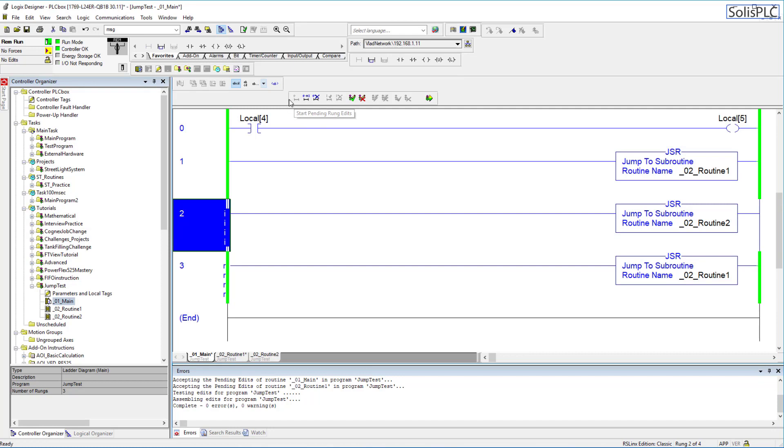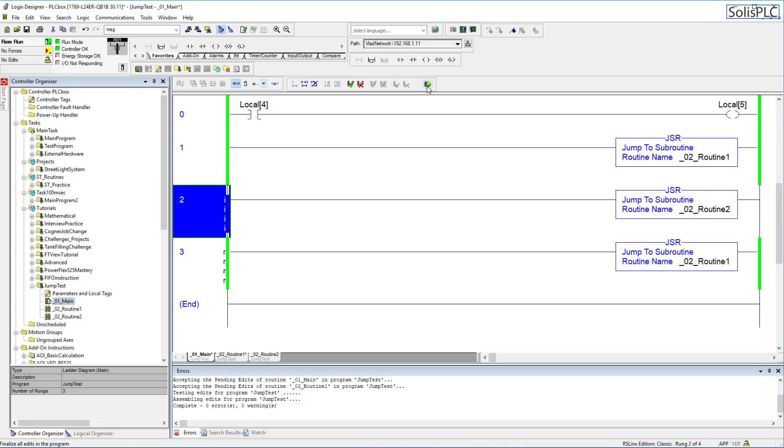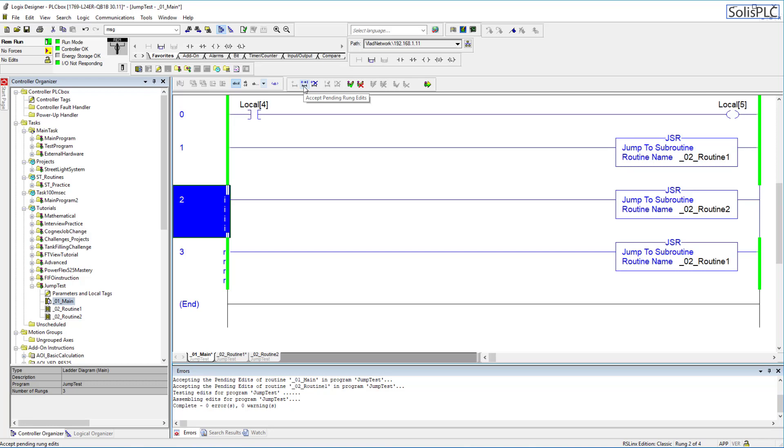Now in order to compile the changes there's going to be several ways. In most cases you will see me use this symbol which is essentially compile all edits in the program. Now this is somewhat of a dangerous move if you're working on live equipment. Since my PLC is just sitting in a box behind me it's no big deal but essentially what this does is that it accepts all pending changes. Now I know exactly what I'm changing and I'm usually doing incremental changes so it's not a big deal but if you have running equipment what I would recommend is I would accept pending rung edits like so. You'll notice that the letters did change and then I'm going to select this test accepted program edits.